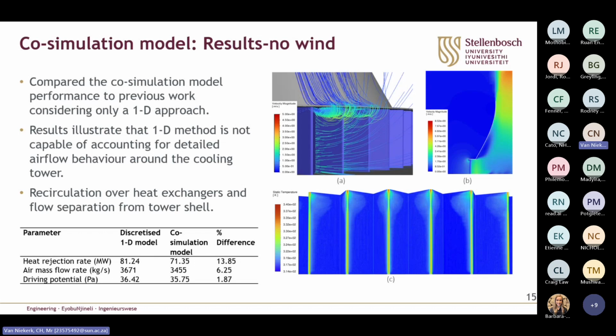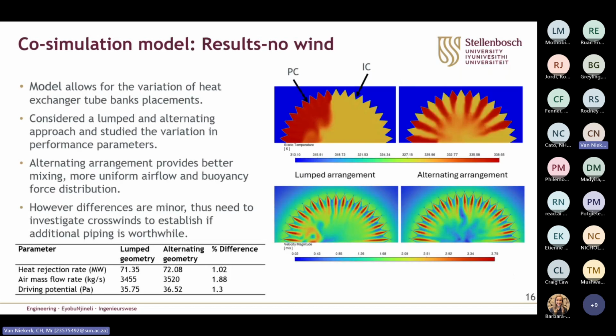And furthermore, we can see this flow separation from the internal tower shell, which causes a further reduction in overall heat transfer. So we could also use the co-simulation model to study varying the locations of the different heat exchanger tube banks around the circumference of the tower. And the first configuration we looked at was a lump configuration where the pre-cooler tube banks and intercooler tube banks are grouped together. And the second one was an alternating approach where the different tube banks are interspersed.